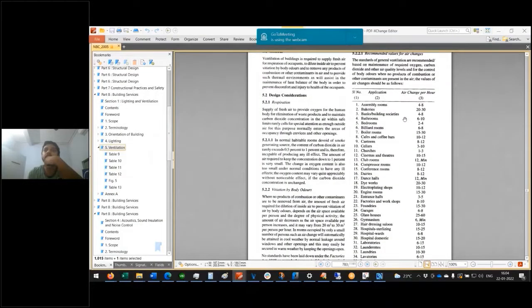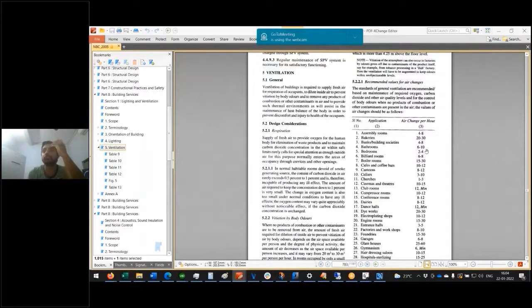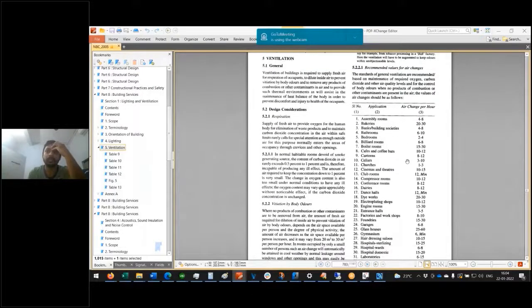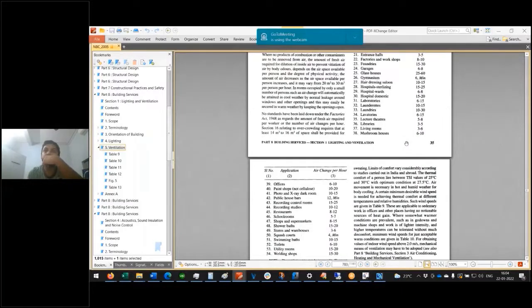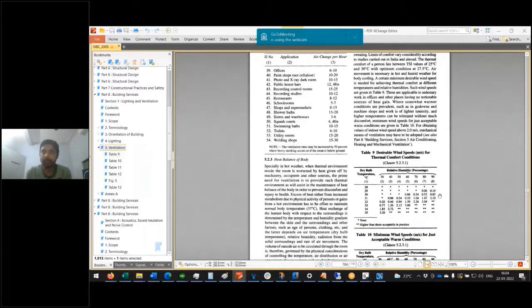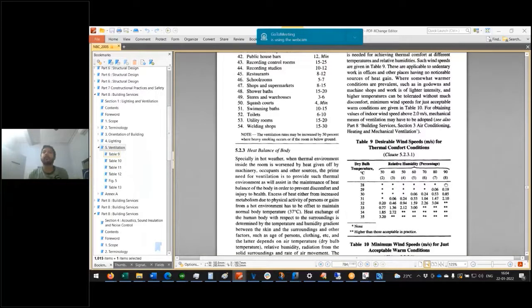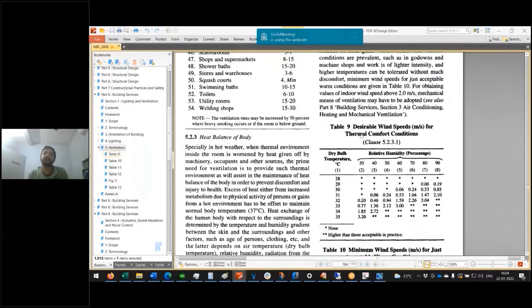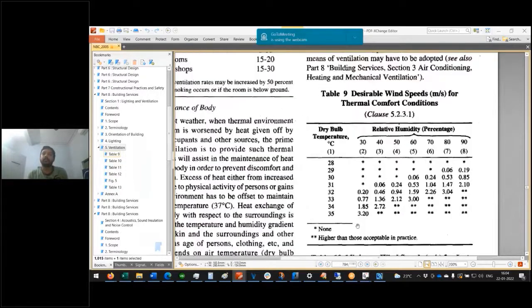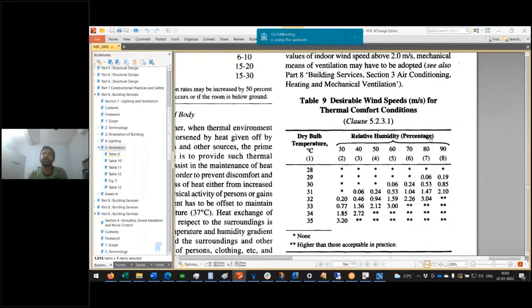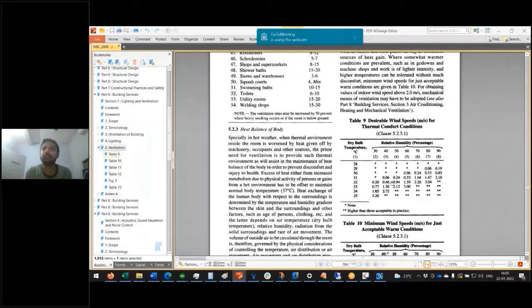So this is what recommended values for ventilation. Maybe you can use this chart, air changes per hour. And this is the chart that I was talking about. Table 9, desirable wind speeds for thermal comfort conditions. So based on the dry bulb temperature and the relative humidity, you have the velocity. These are the velocities which you need to make sure are provided within the space. So that simple calculation you would have to do.